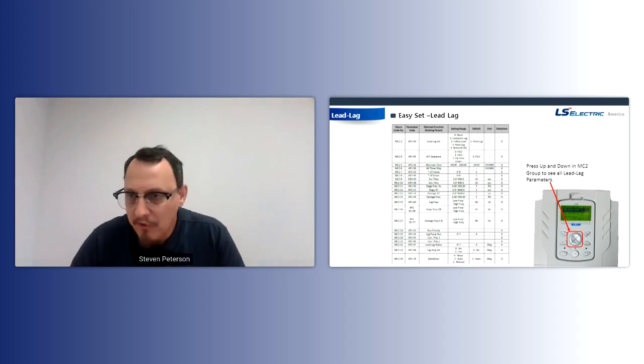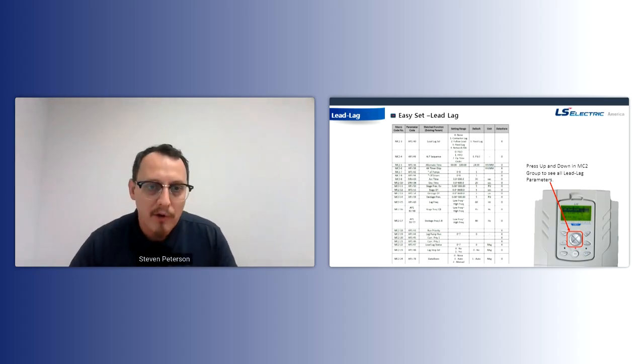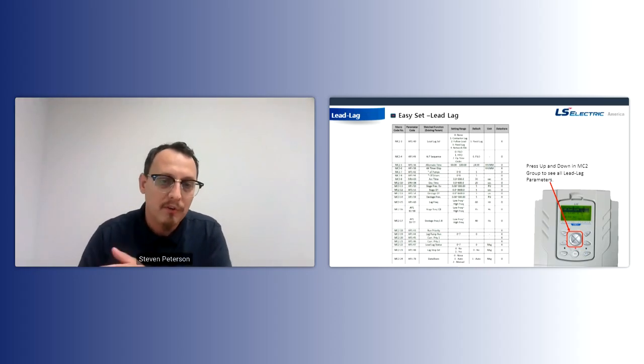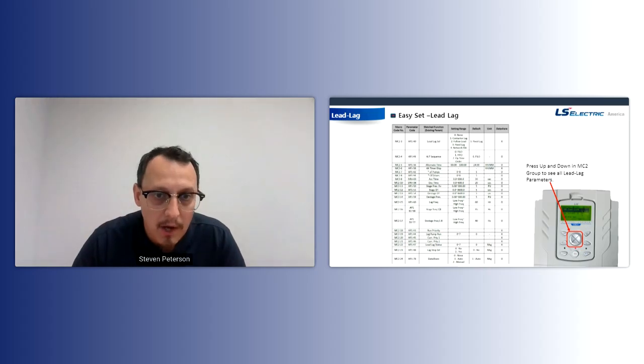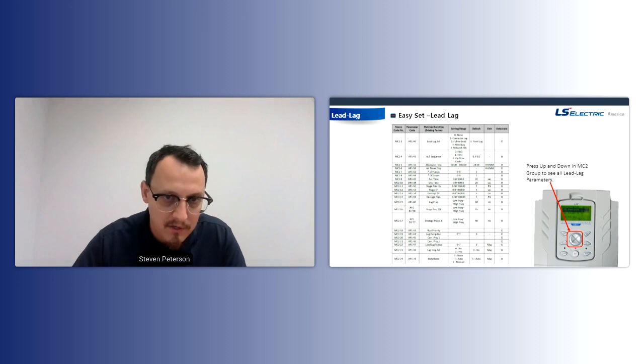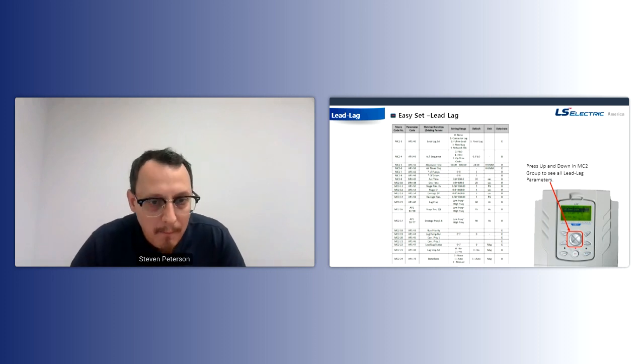A lot of times, guys are just running 24 hours. So every 24 hours, the pumps switch. That's one way to mitigate pump wear, so this one's not coming on all the time. We're actually switching it every day. So that's customizable. You go in here, you set up your number of pumps.